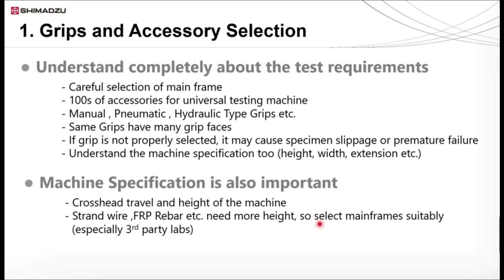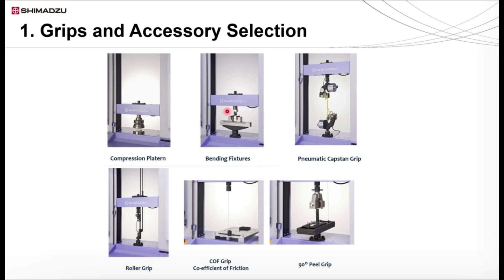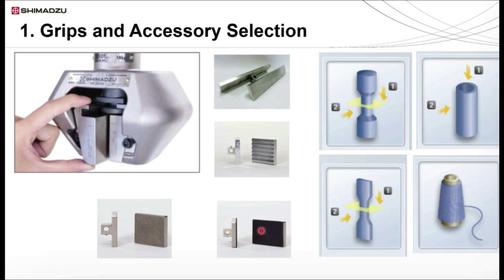As you can see in the picture, apart from normal tensile grips, there are many grips possible with a universal testing machine: compression platen, bending fixture, roller grips, coefficient of friction, peel, shear, tear, etc. So select the most suitable grips according to your test requirement, and equally important, deselect the grips which you don't want. As I mentioned previously, sometimes the grip might be the same, but grip faces are different. So make sure that you purchase a grip which best suits your samples. Get the advice from the supplier in advance.